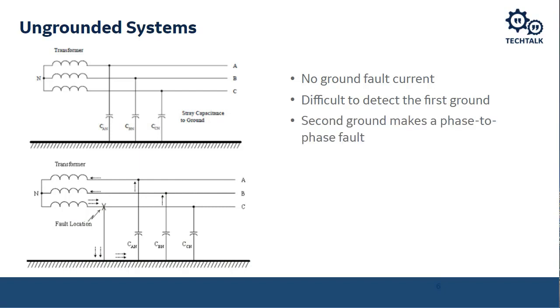But if a ground fault happens, we don't want it to evolve. It's an unlikely scenario, but the probability is there that it might happen, that the fault then evolves to a multi-phase fault, because we're going to be stressing our insulators, we're going to be stressing some of the equipment because they're going to be subjected to transient overvoltages, and that might cause other issues and cause a multi-phase to ground fault. And then once that happens, it can cause massive amounts of fault current to be introduced into our system. So we go from zero fault current to lots of fault current, and that can cause damage to equipment, collateral damage to zones of protection outside of the equipment zone. And we want to avoid these things.